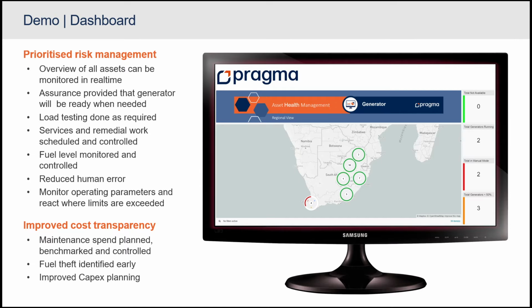On the right-hand side is useful information you can set up as an overview to mitigate risk on a high level, such as the number of generators not available, currently running, or in manual mode, meaning it won't start automatically since it's not in auto mode, as well as generators running low on fuel. You can fully customize this according to your business priorities and set up specific KPIs to manage that.